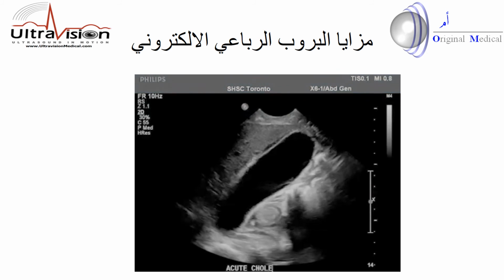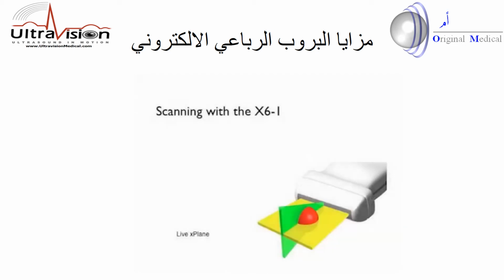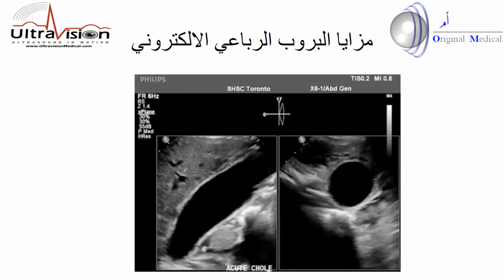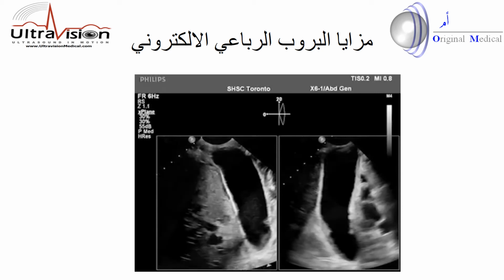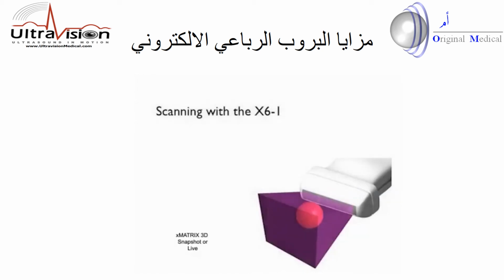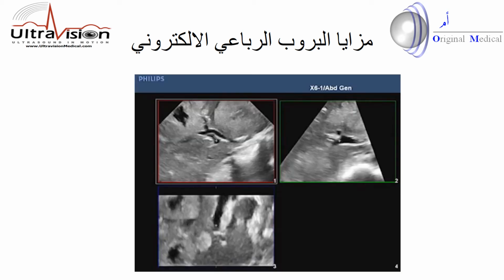But if we look at this gallbladder, for example, with the X6-1, we can also go immediately into a real-time mode, the X-plane mode, and see two orthogonal views of the organ simultaneously. Here a long axis and a short axis, and here, just by moving the transducer, two orthogonal long axes. So that's X-plane imaging. And we can also use the transducer to acquire all of the data. And again, this can be done live or in a snapshot.